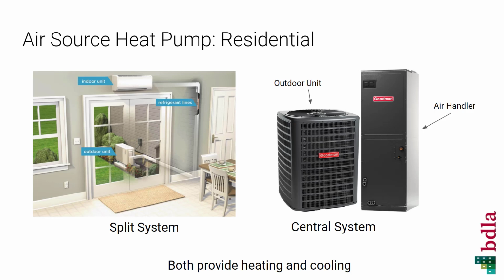Air source heat pumps are also used in residential applications. This is a slightly different application. The outdoor unit and the indoor unit are both components of the heat pump, where the outdoor unit is able to reject heat outdoors or pull heat from the outdoors, which heats up refrigerant. The refrigerant is then piped to the indoor unit, where it's able to heat or cool the indoor space. The central system is a similar application, but instead of having a small single indoor unit mounted on a wall like you see on the left, this is a more typical central air handler, which is distributing hot or cold air throughout ducts.